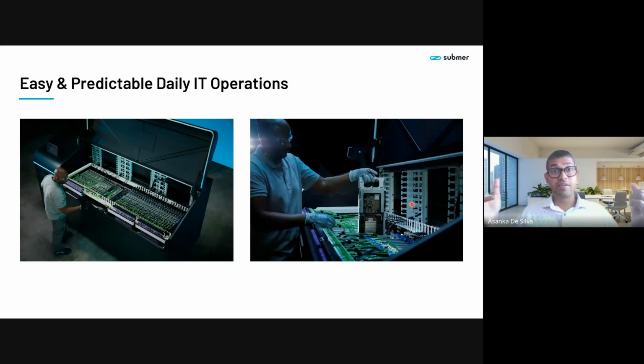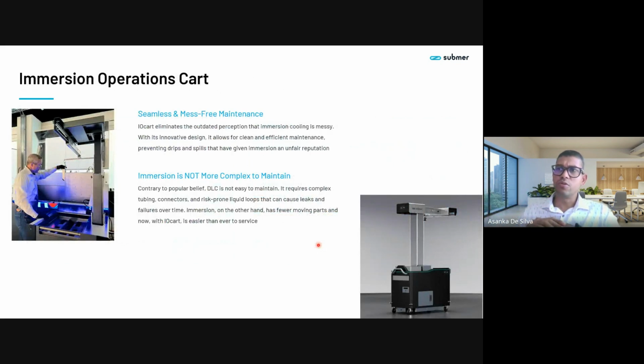Okay, so what does this mean? This means when your failure rate of the servers reduces to that level, the interactions with the servers are less. That means you have less requirement for maintenance to start with, right? So there are a couple of important things when it comes to maintenance and immersion cooling. There's less need for operations, number one. Number two, how can we optimize the few operations needed on the system? In order to do that, we've introduced something called an operations cart. This is how it's going to look. It'll be released in about 3 to 5 months or so. It's a patented product for Submer.